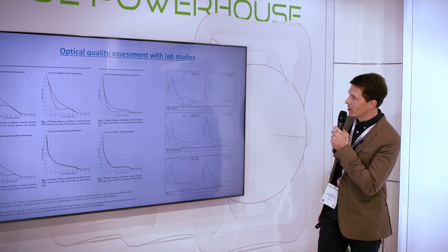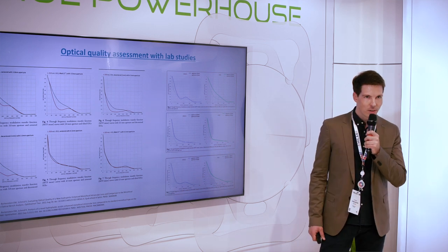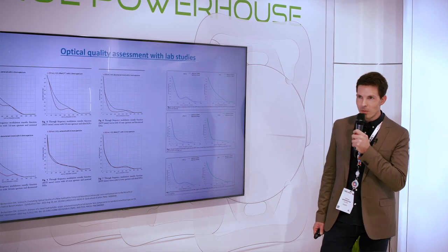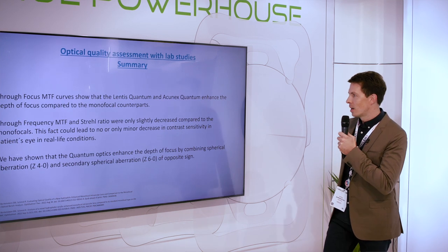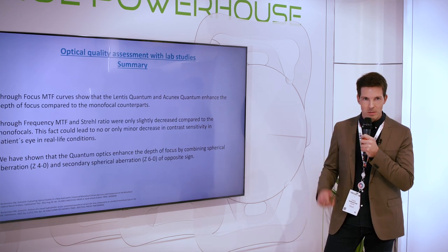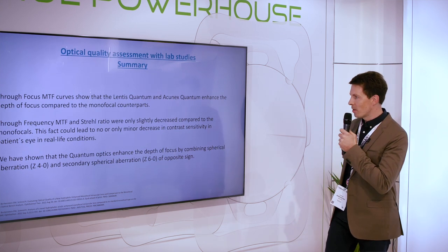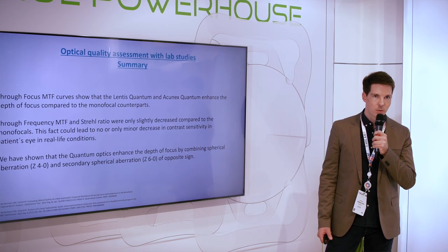We evaluated the modulation transfer function and the Strehl Ratio to get an assessment of optical quality and to see if the company's claims are true. What we can summarize is that the through-focus MTF curves of both Lentis Quantum and Acunex Quantum enhance the depth of focus compared to the monofocal control lens, and the through-frequency MTF and Strehl Ratio were only slightly or not decreased compared to the monofocal. This could lead to very good real-life behavior, meaning contrast sensitivity is equal to the monofocal lens.